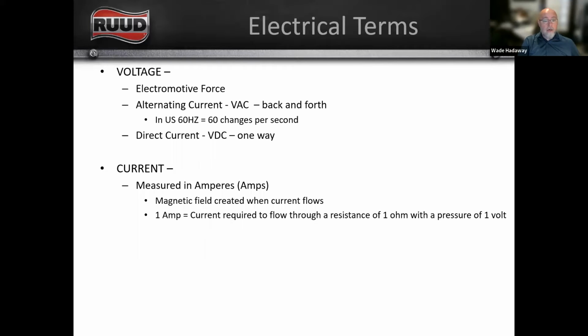So that's voltage. So current is measured in amps or amperes. And when we're measuring current, you have your multimeter, and we'll look at a multimeter here in just a second. When you clamp the jaws of your multimeter around any conductor, any wire, what you're measuring is the magnetic field that gets created as current is flowing through. As those electrons are moving through that conductor, it creates a magnetic field, and the intensity of that magnetic field is what we call amps or current. So when you clamp your meter on, you're measuring the intensity of that magnetic field that's created around that current.